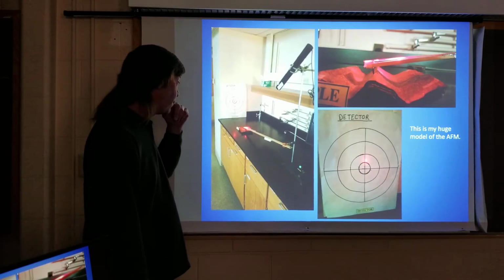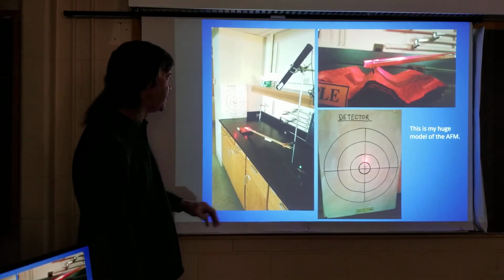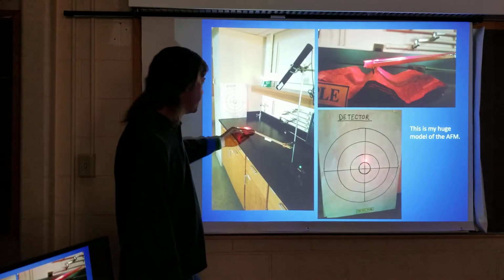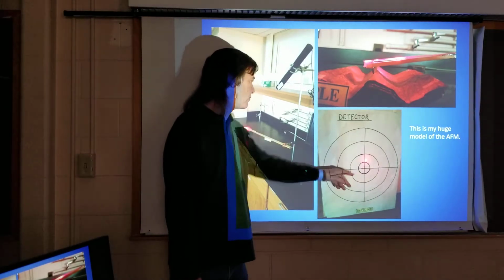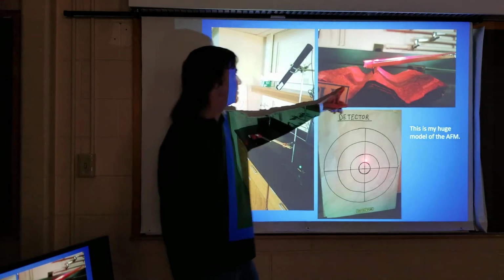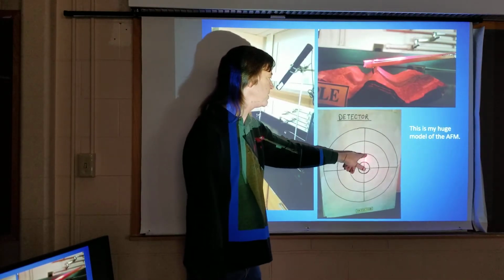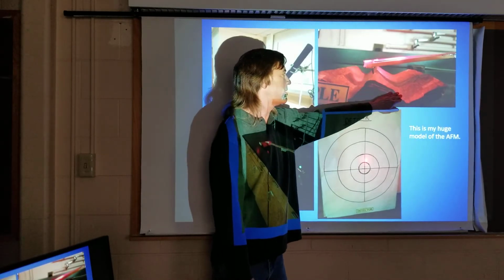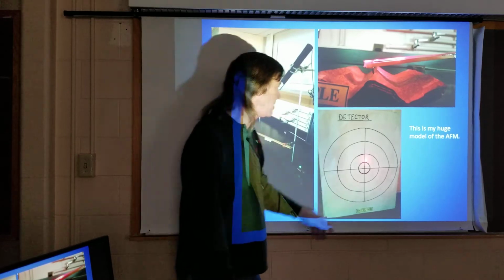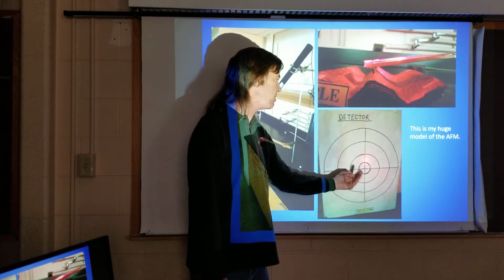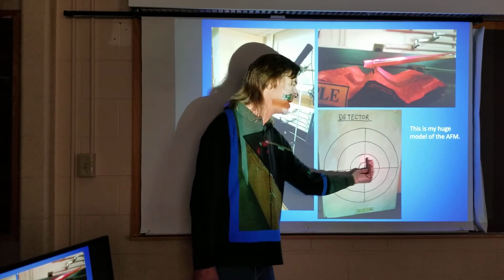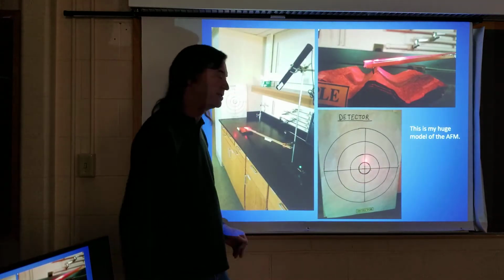And on the video, it's hard to see the reflection, unfortunately, but when I had it on a mid spot, it was right in the middle. When I had it going over a tall part, like this part right here, this raised up, of course, and the beam went up here. When I went down to the very bottom part, that's when this guy went down. So we can see that the detector is going to measure not only the height, but also this direction as far as the angle of that particular data point.